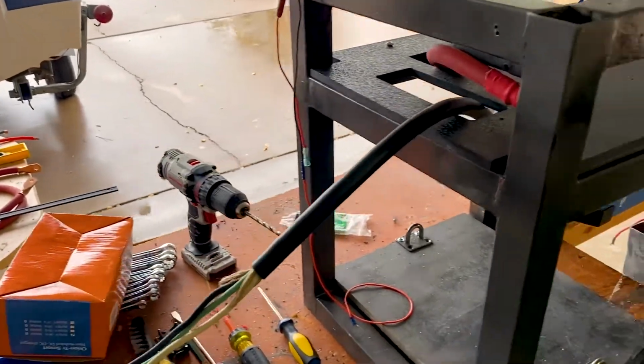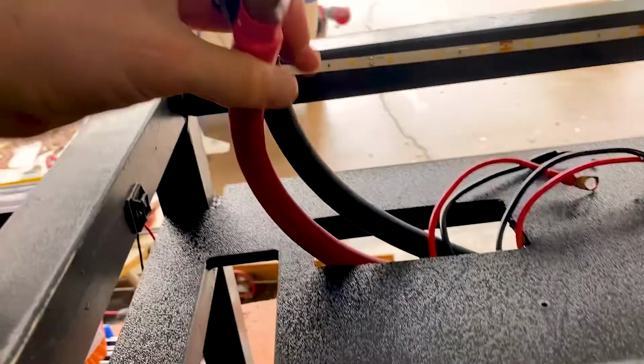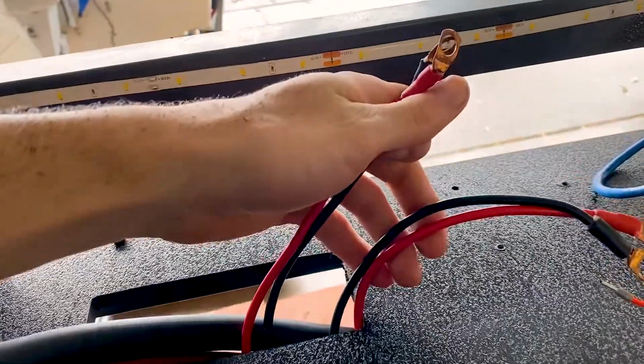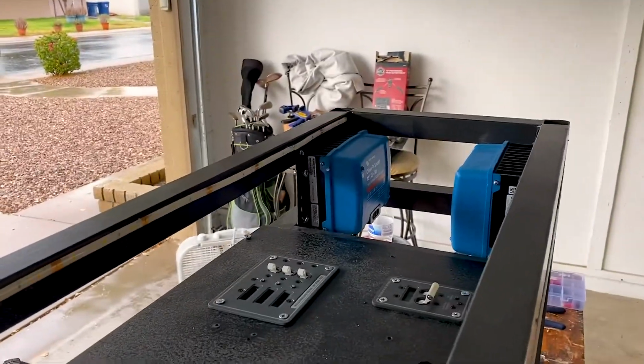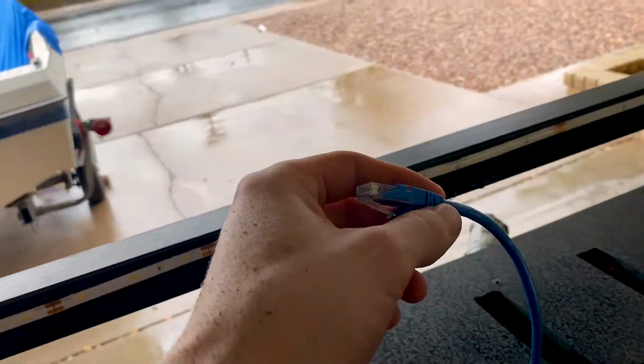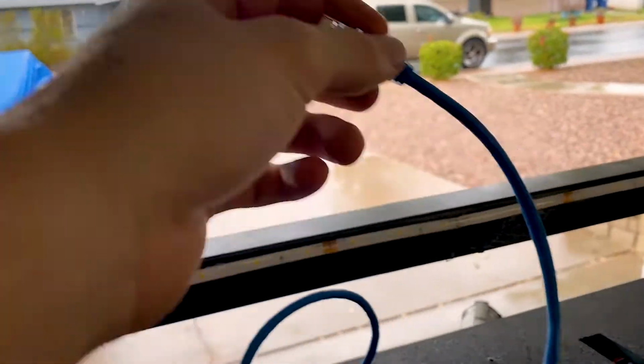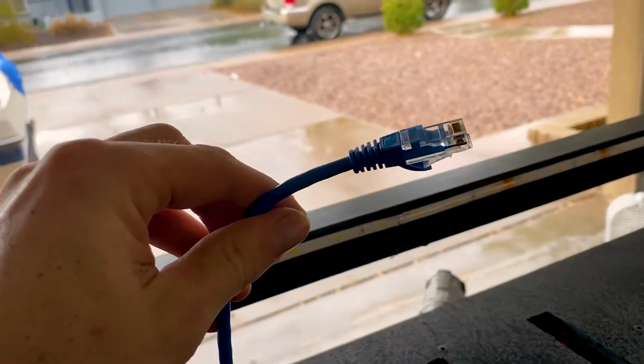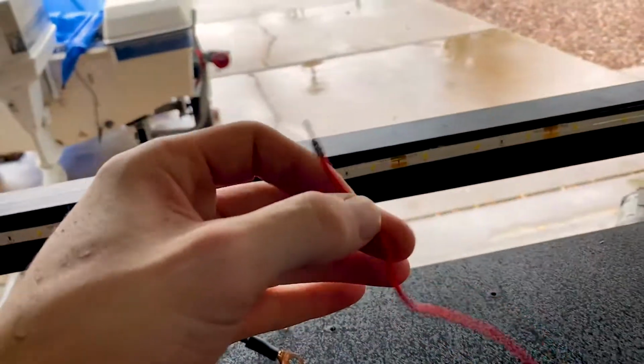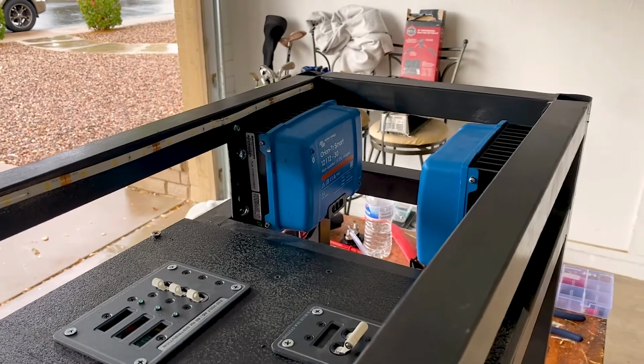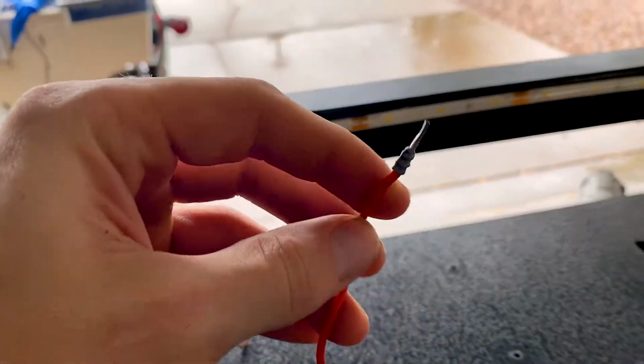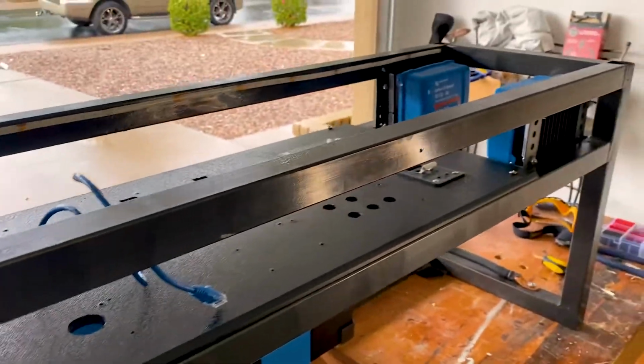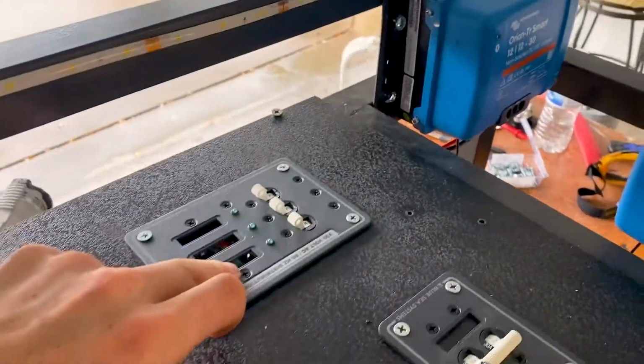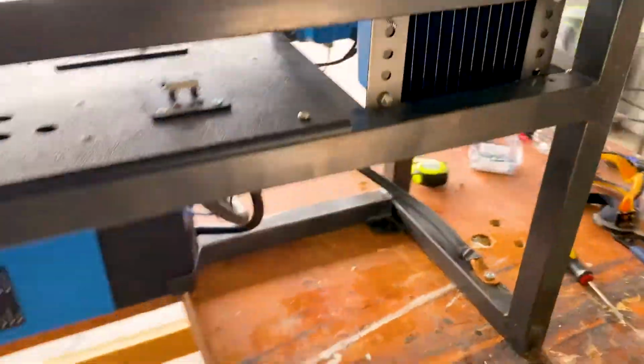We got our 10-3 wire connected to the AC circuit breaker, which will power our outlet. We have our 4-gauge wire coming from the inverter there. We have our two 10-gauge positive and negative wires from the Orions, already pre-fed. That is an RJ45 cable, connected inside the inverter where it says VE bus, which will connect straight into the Cerbo GX, which you'll see later. That is the H-pin connection from the Orions, which will get plugged directly into the Lynx Smart BMS. And now we've got our AC breakers right there, and the AC main on-off switch.